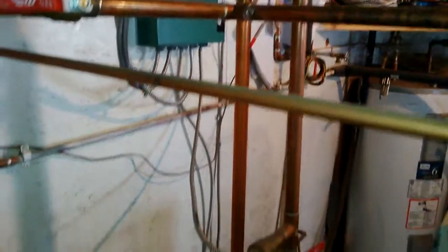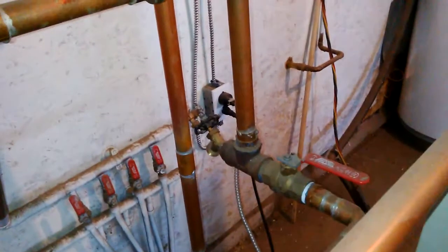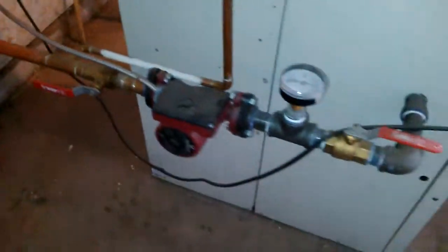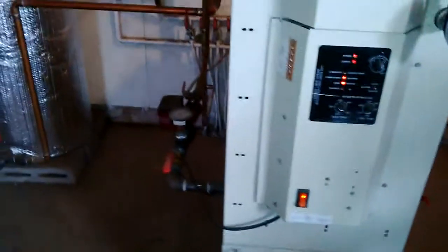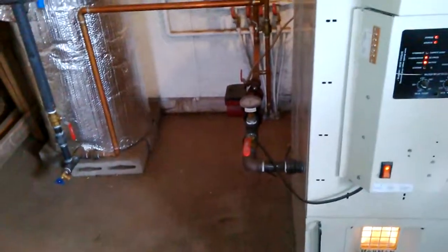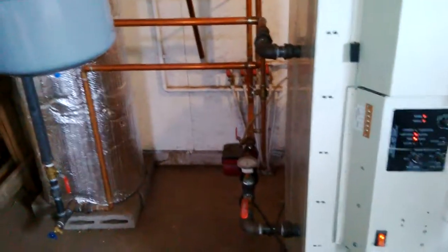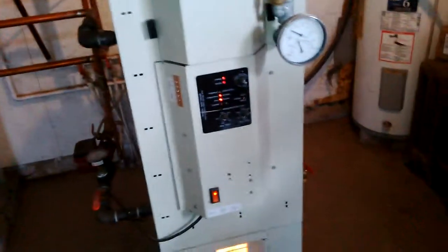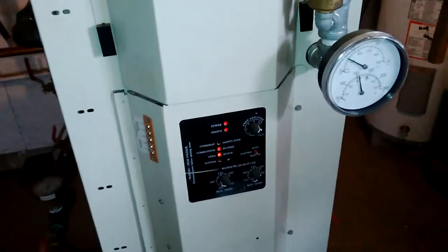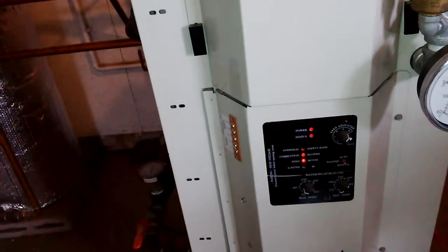The return goes down into a circulating pump, which I just have plugged into a wall receptacle. You could plug it into the front into your dump zone, but basically all that does is constantly circulate the water between the Hydroflex 60 and the 60-gallon hot water tank. That allows me to use the aquastat that's in the Harman Hydroflex to maintain the temperature in the buffer tank.